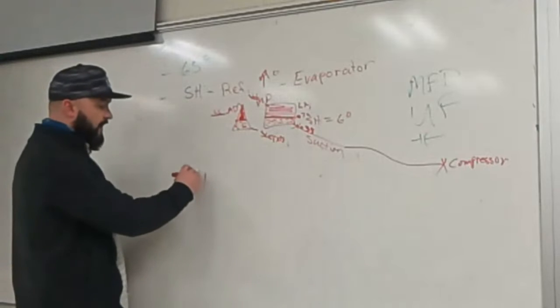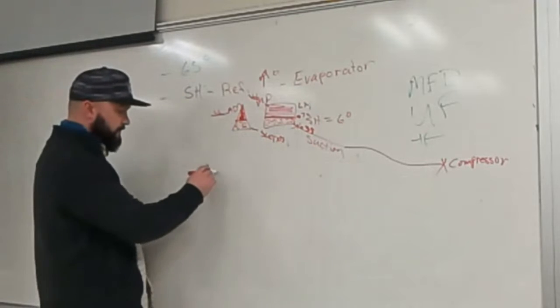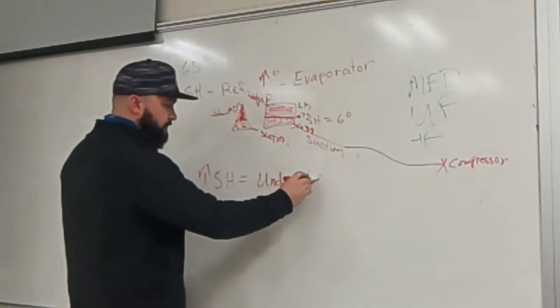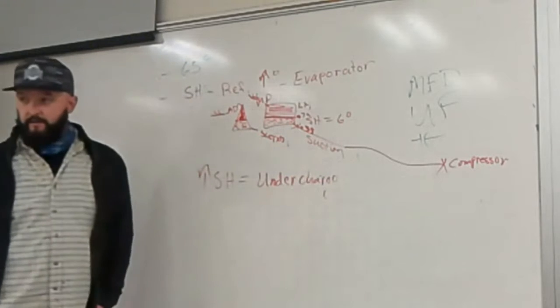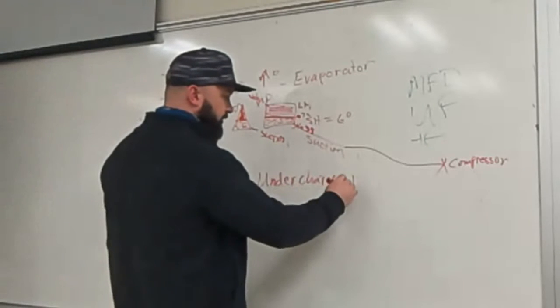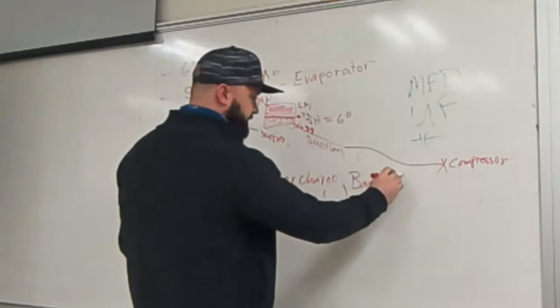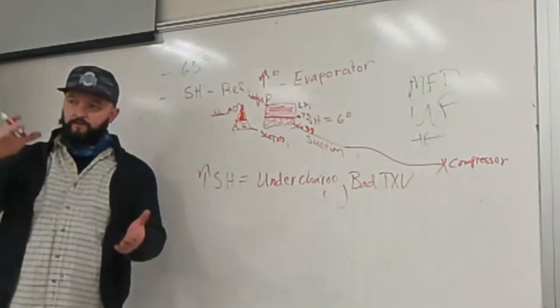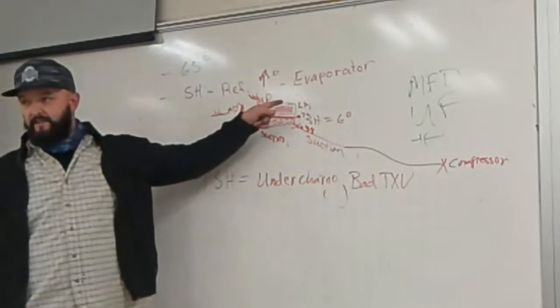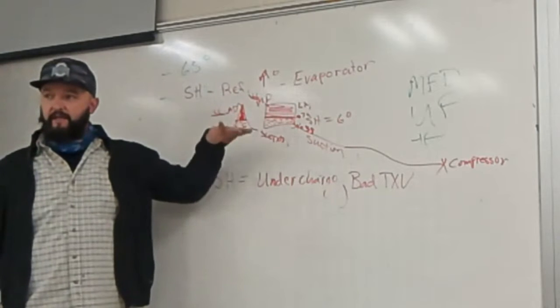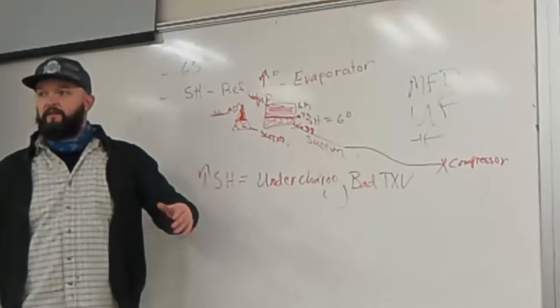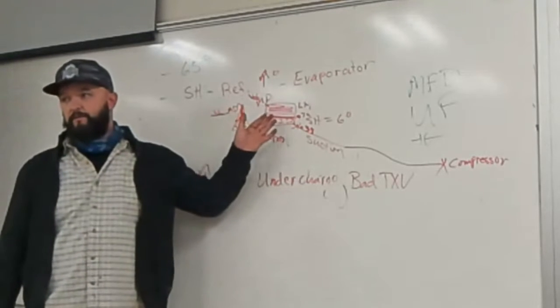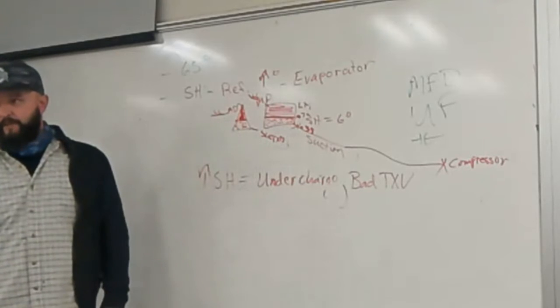For most purposes, reading at the compressor is close enough. Here's what superheat tells you: high superheat equals undercharged, or a bad TXV. The TXV is supposed to open and close to control what it feeds into the coil. If it floods the coil, the refrigerant can't fully change from liquid to gas, and if it starves the coil, you won't have accurate superheat.